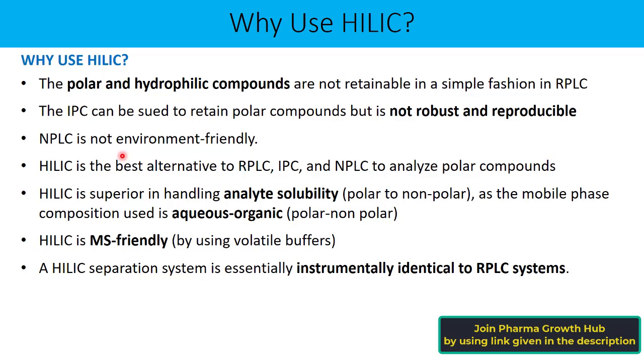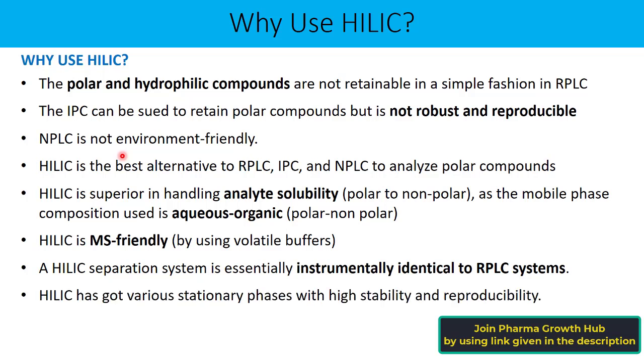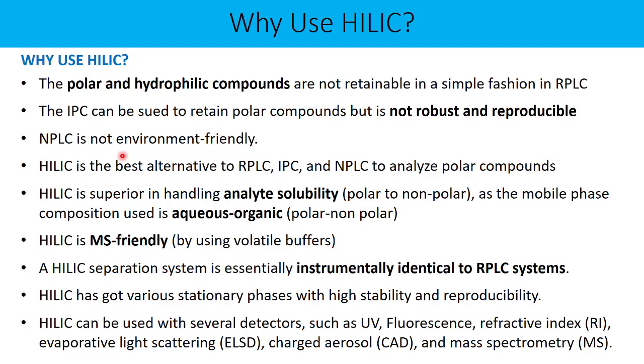A HILIC separation system is essentially instrumentally identical to an RPLC system. The mobile phase composition is almost similar — organic plus aqueous in both cases — so there is no significant difference as far as the instrument is concerned. Only the column (stationary phase) is different, which is not part of the HPLC instrument itself. HILIC offers various stationary phases with high stability and reproducibility. Last but not least, HILIC can be used with several detection techniques including UV, fluorescence, RI, ELSD, CAD, and mass spectrometry.